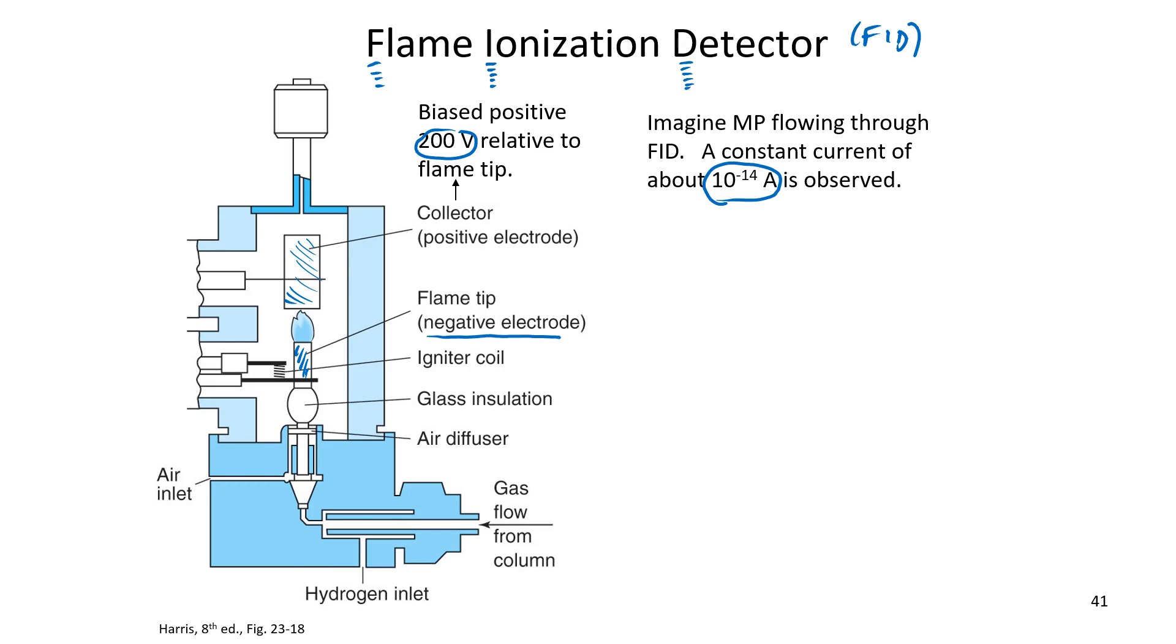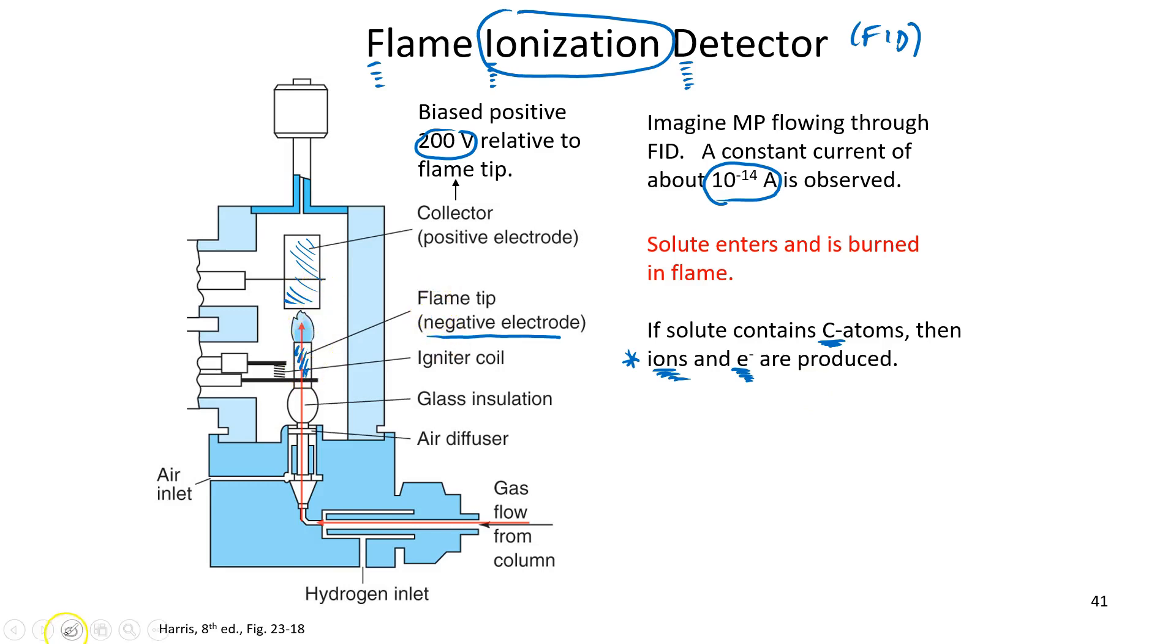And what happens when our solute enters? It gets burned. And if that solute contains carbon atoms, ions and electrons are going to be produced, hence the name ionization. And what do you think the presence of these ions and electrons do to the current across the flame tip and the collector electrode?